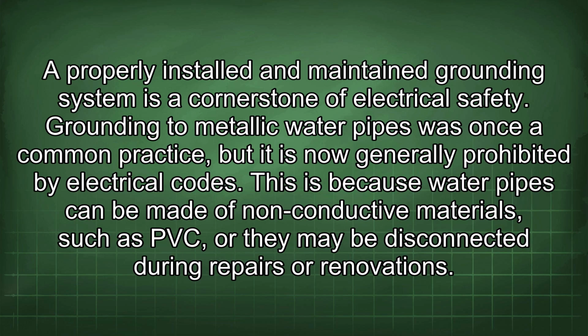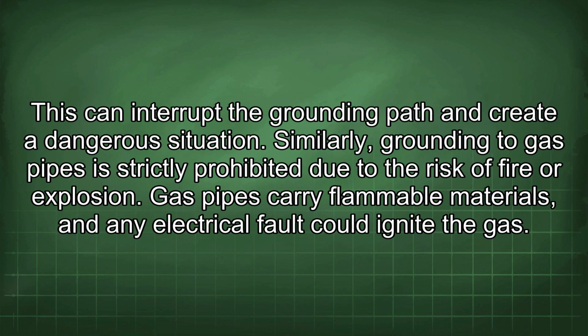Grounding to metallic water pipes was once a common practice, but it is now generally prohibited by electrical codes. This is because water pipes can be made of non-conductive materials such as PVC, or they may be disconnected during repairs or renovations. This can interrupt the grounding path and create a dangerous situation. Similarly, grounding to gas pipes is strictly prohibited due to the risk of fire or explosion. Gas pipes carry flammable materials, and any electrical fault could ignite the gas.